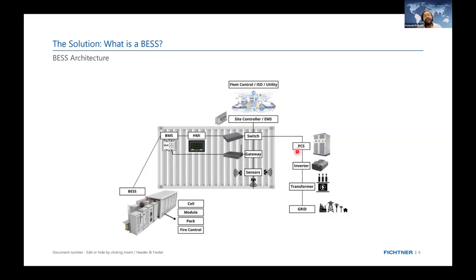For that we have the PCS, power conversion system - it's nothing but a bidirectional DC-DC converter inverter, or DC-AC converter inverter. The DC system has a bidirectional DC-DC converter, which might be a chopper, or a dual active bridge, or multi-stage dual active bridge, DABs, anything for DC systems. But if it's an AC system, I need DC-AC inverters - currently in research, neutral point clamp inverters are quite good, three-phase inverters. So at one end it's DC, the other end AC, but all bidirectional.